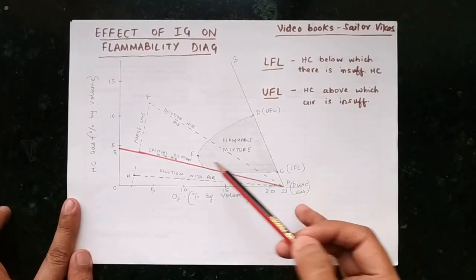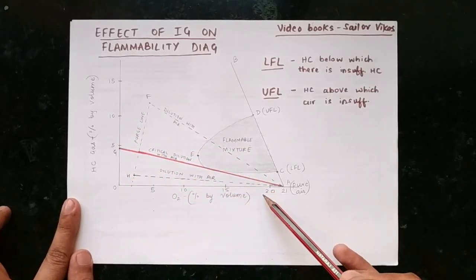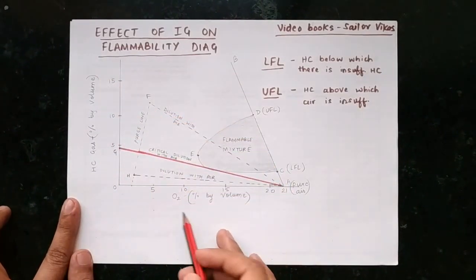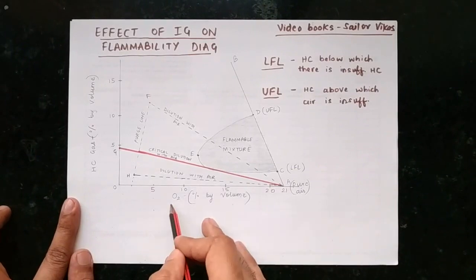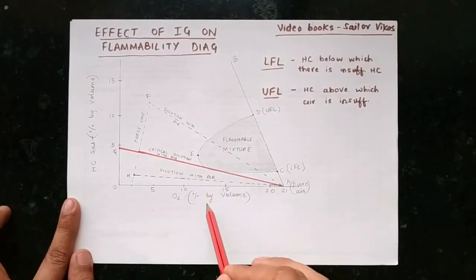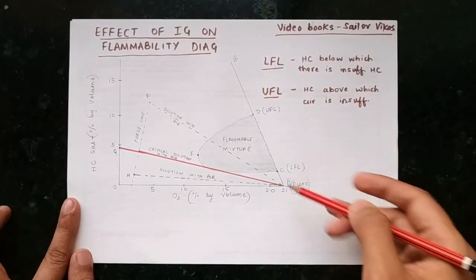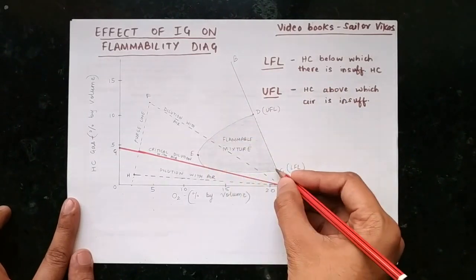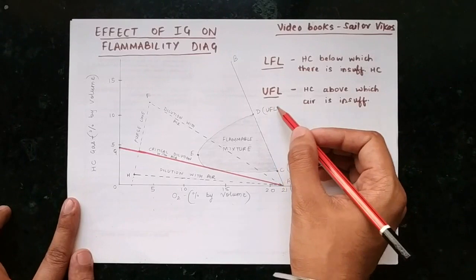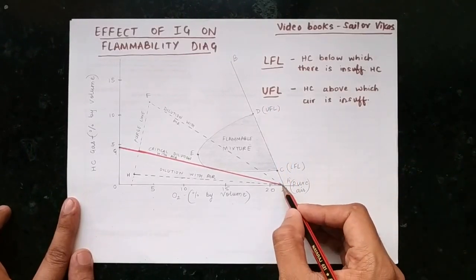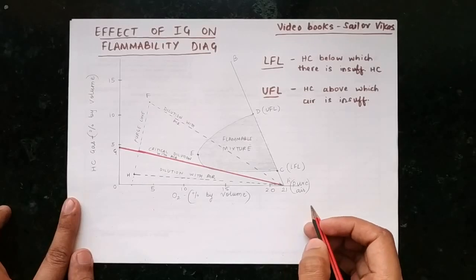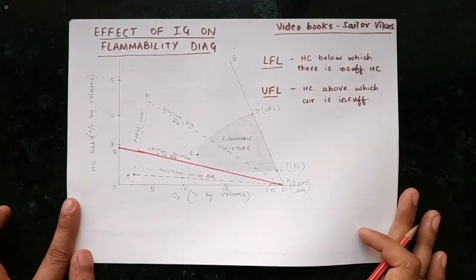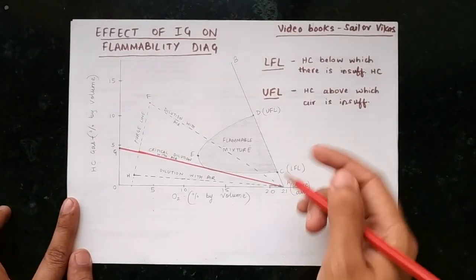I will introduce you to all the basic things in this diagram. The y-axis represents hydrocarbon gas percentage by volume, and the x-axis represents percentage by volume of oxygen. There is one sloping line A-B, and here is your flammable mixture region. This is the lower flammable limit, this is the upper flammable limit, and here is point A which represents pure air.